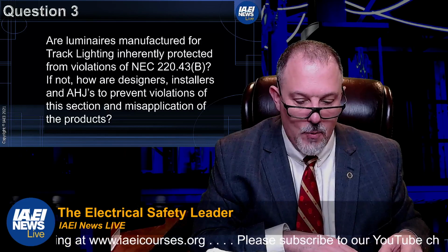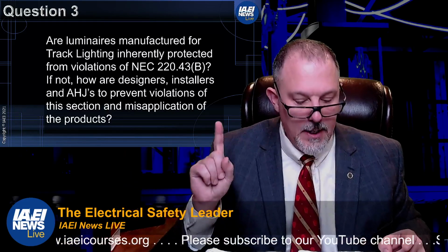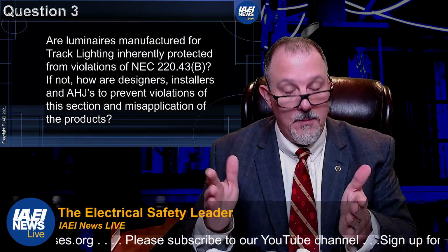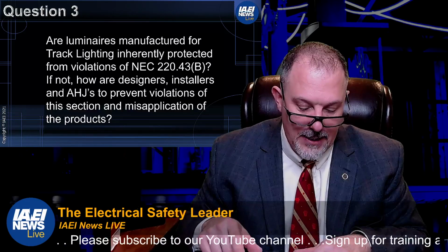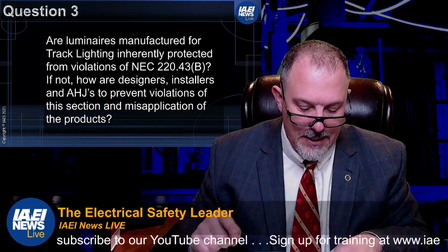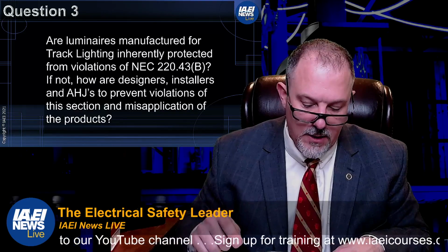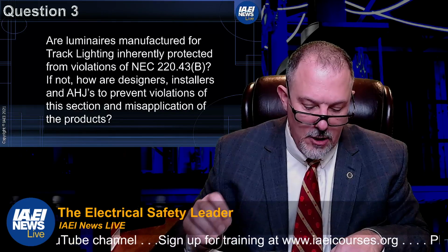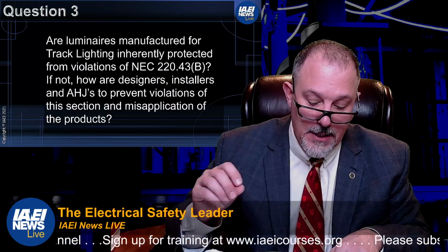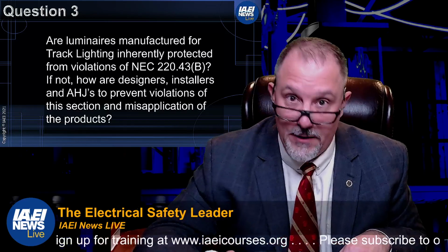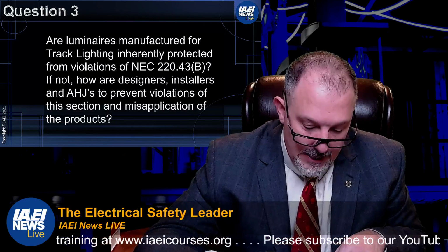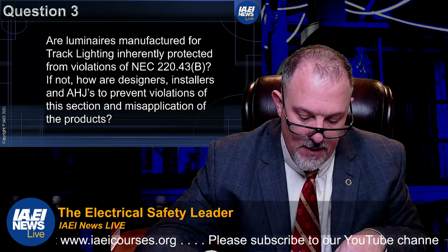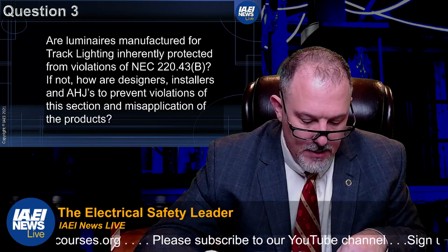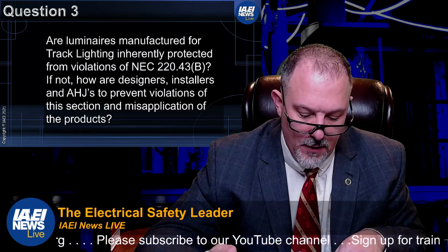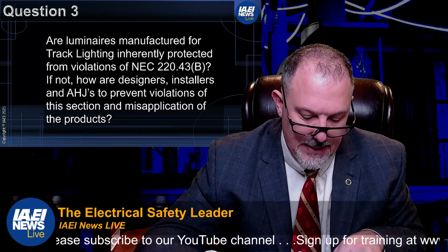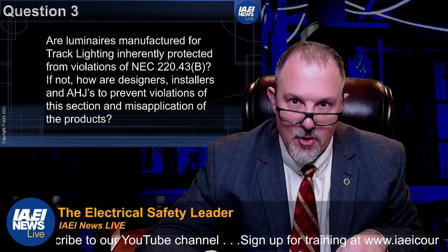A talks about show windows, not what we're talking about. B talks about track lighting. So now let's read B. For track lighting in other than dwelling units or guest rooms or guest suites of hotels or motels, an additional load of 150 VA shall be included for every 2 feet of lighting track or fraction thereof. Where multi-circuit track is installed, the load shall be considered to be divided equally between the track circuits.